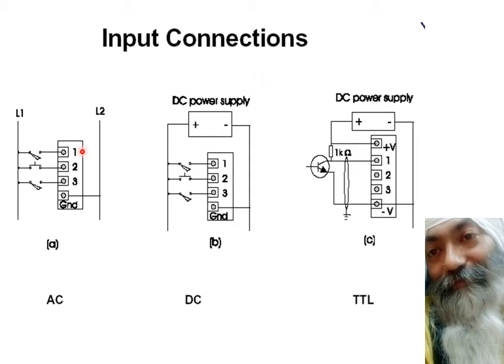You can see there's a switch over here. It can be a normal switch, limit switch, or push button. It goes directly in case we are providing a voltage which is acceptable. In case that voltage is not there, we have a potential free contact. We call it a potential free contact. In that case, we have to supply the appropriate voltage, let us say 5 volt, and the common is given to the ground over here, and the voltage is supplied externally.